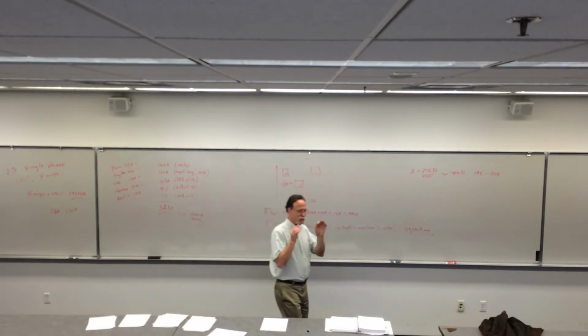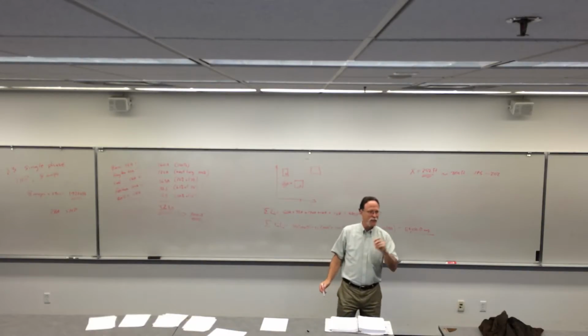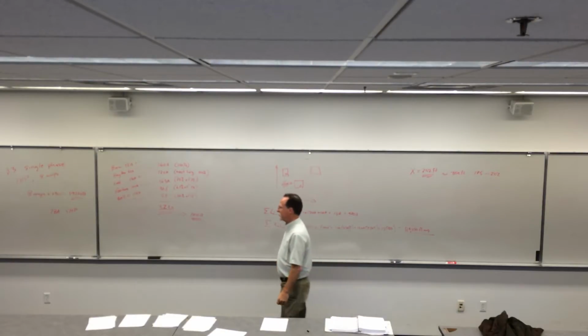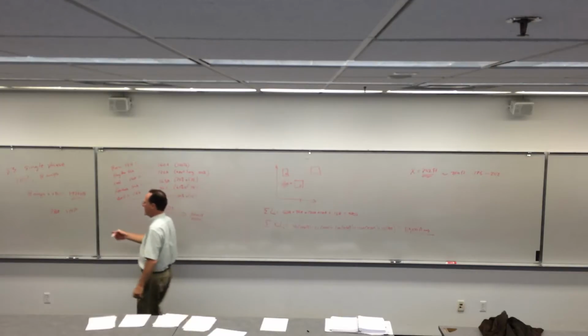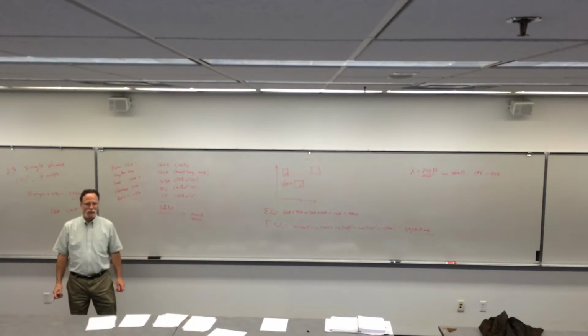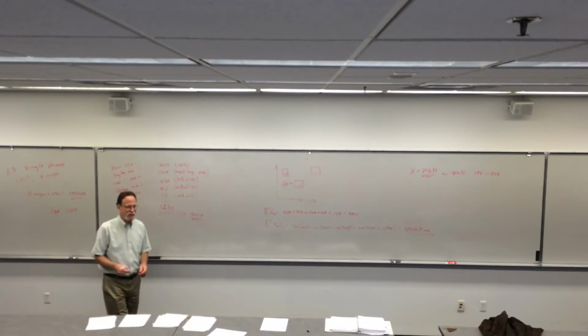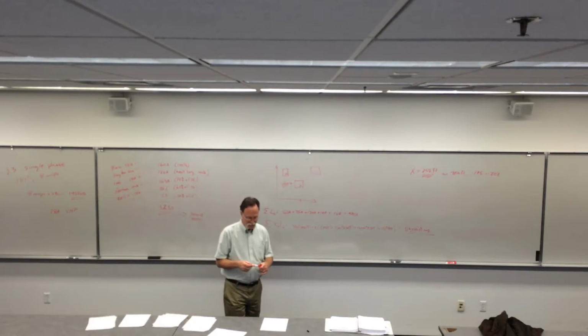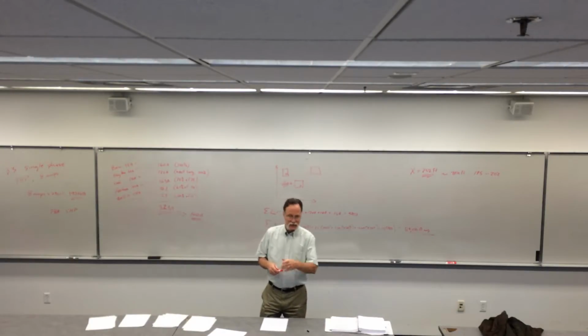What is the minimum ampacity load center for an ag building? 60 amps. Right. So hanging out by itself, I've got a 15 amp disconnect for that motor. I put it in a building, oh crap. Do you really want me to do that? It probably makes you put 60 amps in it. You have a pump house, it doesn't necessarily have to be on an ag place. That's correct.